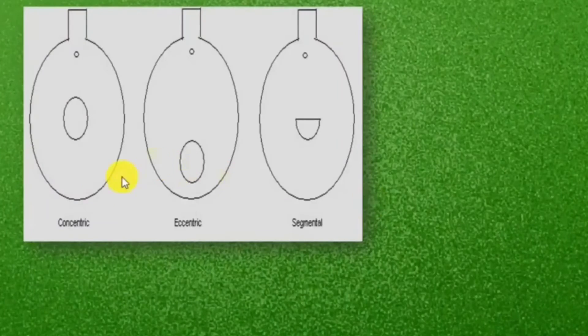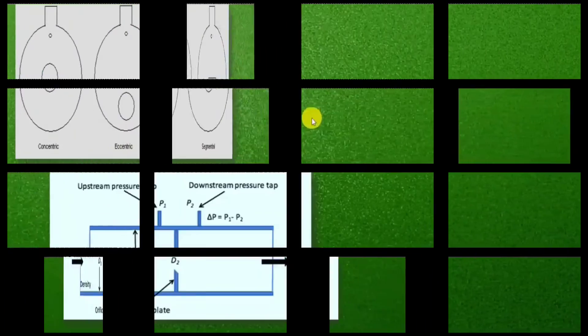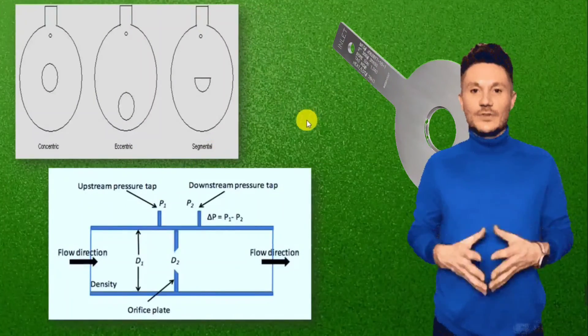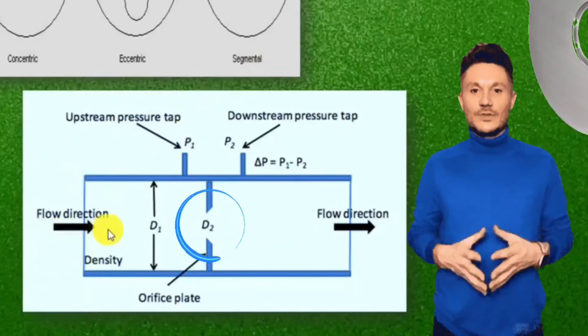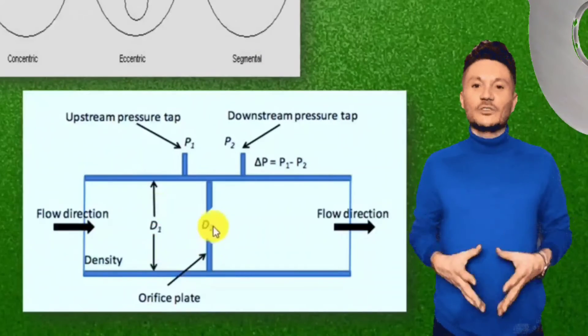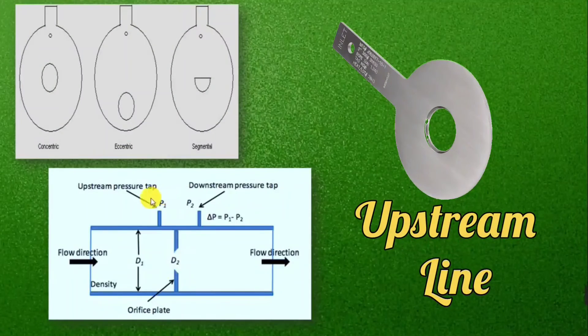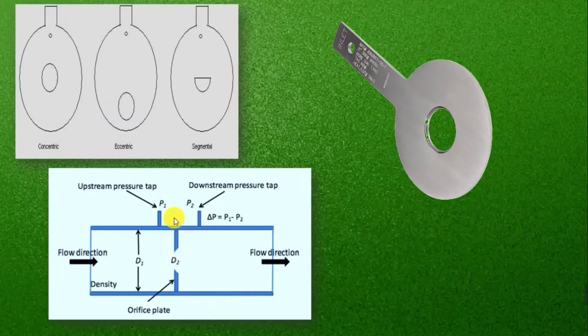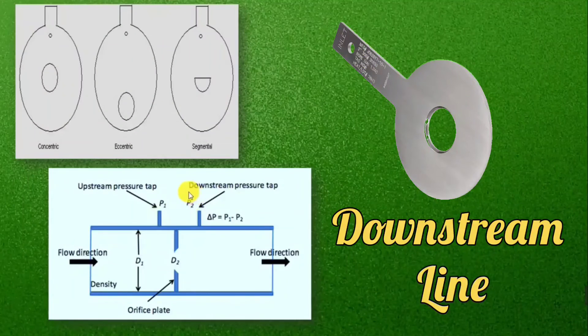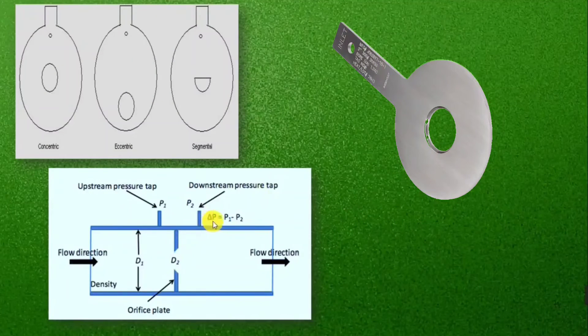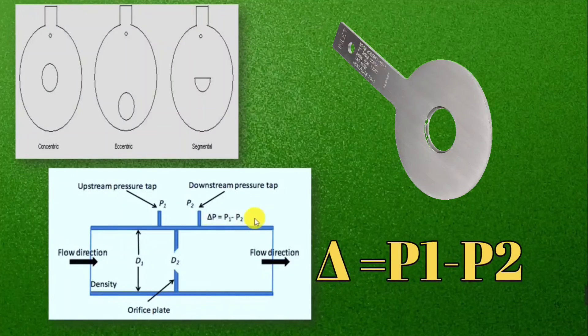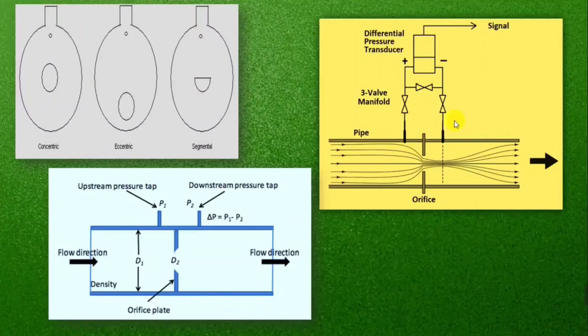In this image, some types of orifice plate are shown — like concentric, eccentric, and segmental. Here you will also understand the use of a flow orifice. This flow orifice is installed in a pipeline. Suppose the diameter of the pipeline is D1 and the diameter of the flow orifice is D2. The pipeline before the orifice plate is the upstream line — suppose pressure here is P1. The pipeline after the orifice plate is the downstream line — suppose pressure here is P2. The pressure difference between them is P1 minus P2, denoted by delta P in this image. An arrangement is shown with a three-valve manifold.